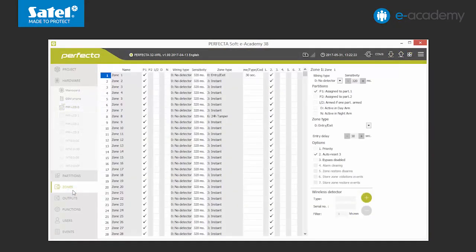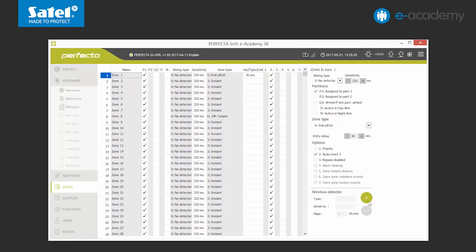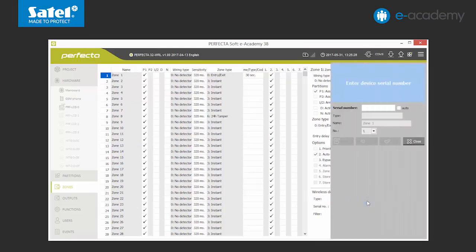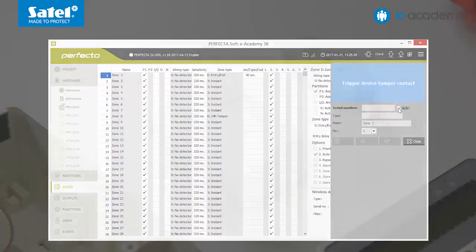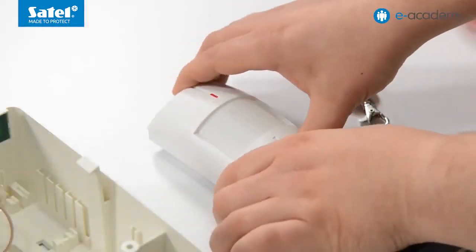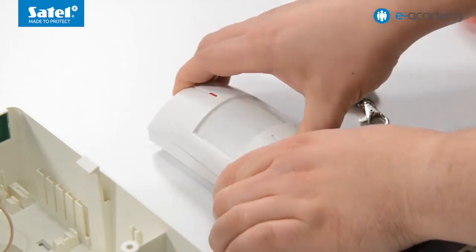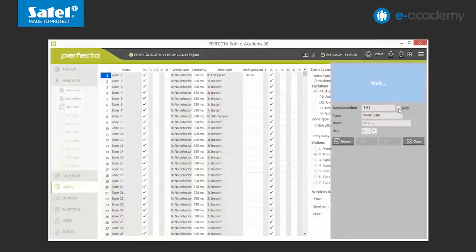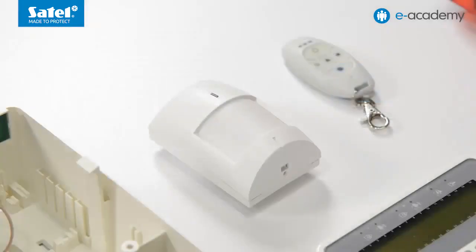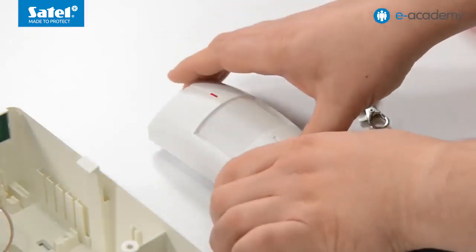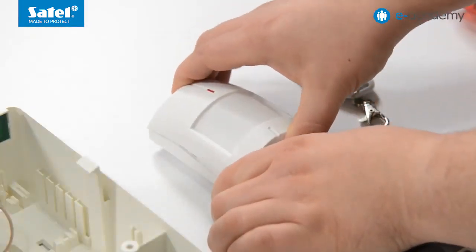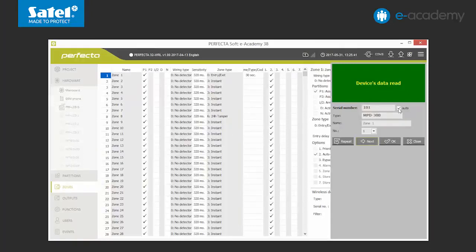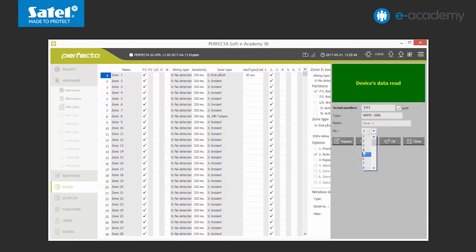We choose one of the zones. The options for wireless detector are available on the list. To add it, we click the plus key. A menu is displayed for adding a new device on the right. We choose the auto option. Now we have to violate the tamper of the added detector. After the new device has been found, the program will automatically fill in its serial number and model. Violate the tamper again. The device has been recognized. We can still change the zone number to which we will assign the detector. We complete by clicking OK.